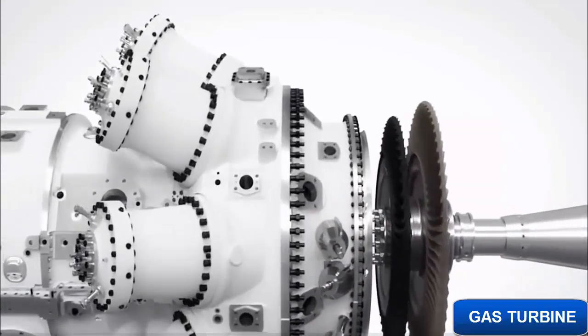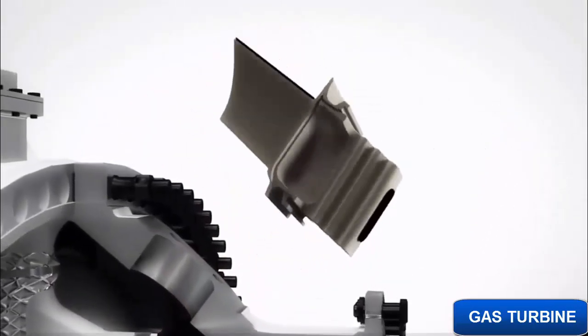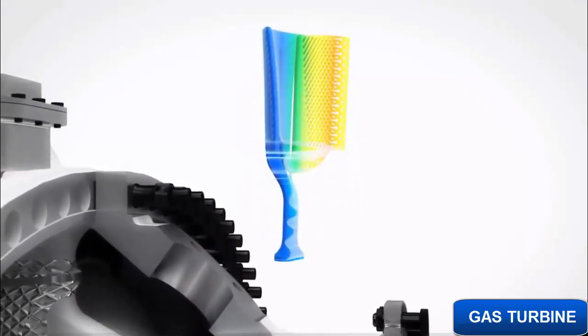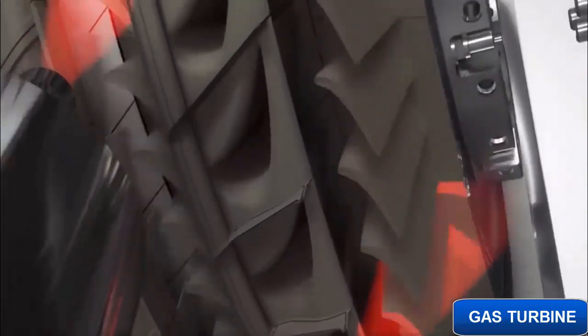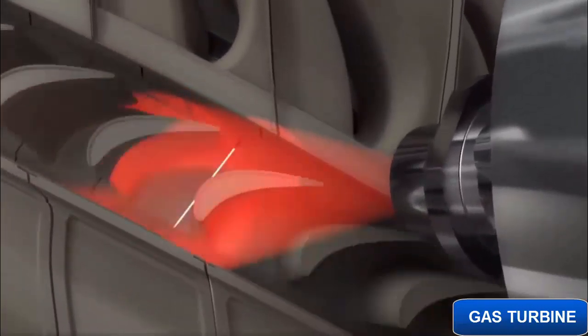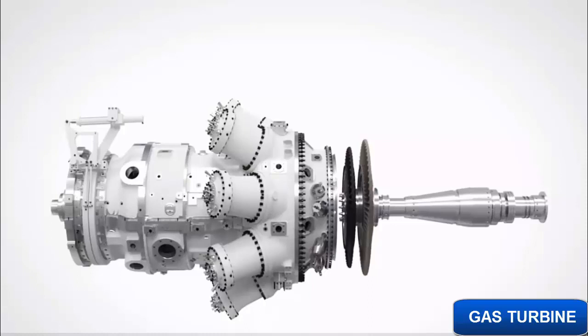Now, let's move downstream to the compressor turbine. The compressor turbine blades are made from conventional materials with several years of proven experience for maximized durability. To ensure perfect performance over time, online monitoring infrared cameras can be mounted on the SGT-750, allowing detailed temperature measurement of the rotating blades. All SGT-750s are mapped with the online monitoring IR cameras during engine delivery tests and later verified during regular scheduled inspections.